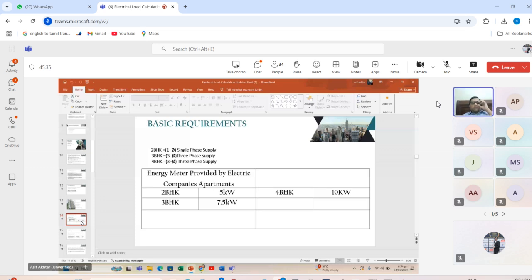Single-phase supply will be used in 2 BHK apartments, and 3-phase supply will be used in 3 BHK apartments. The energy meter is provided by the electrical companies. For any 2 BHK apartment, electrical companies in the Middle East will provide you a 5 kilowatt energy meter. And if you have a 3 BHK apartment, the electrical company will provide you a 7.5 kilowatt meter. It is basically for your load.